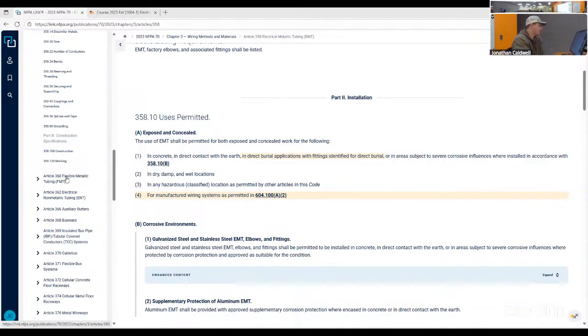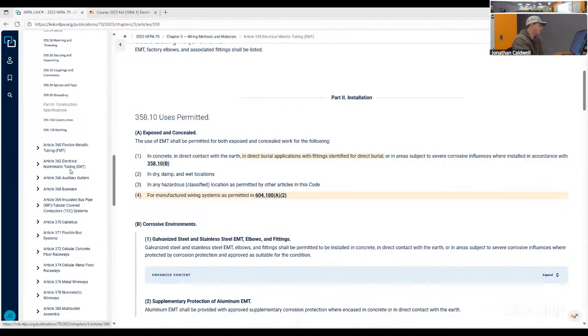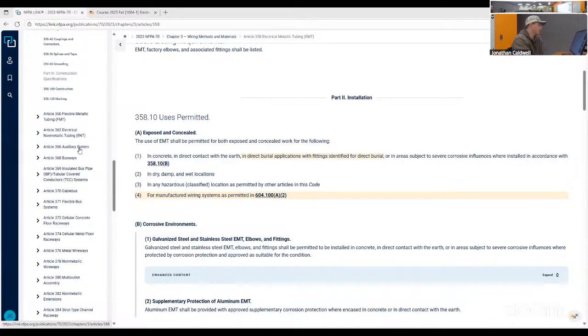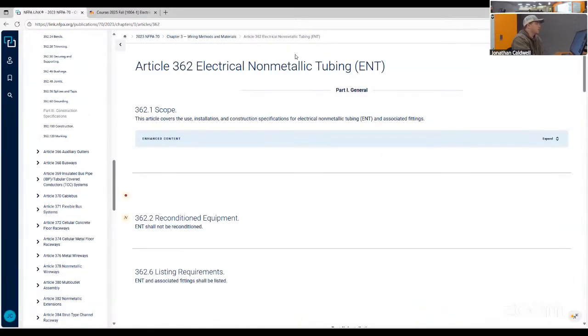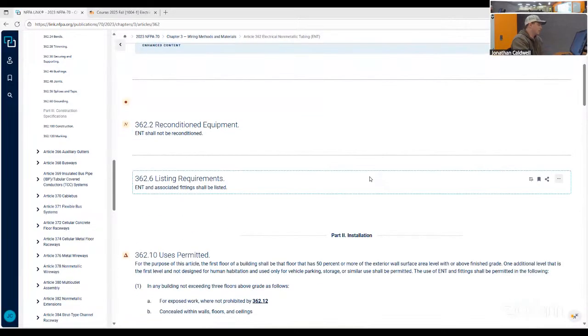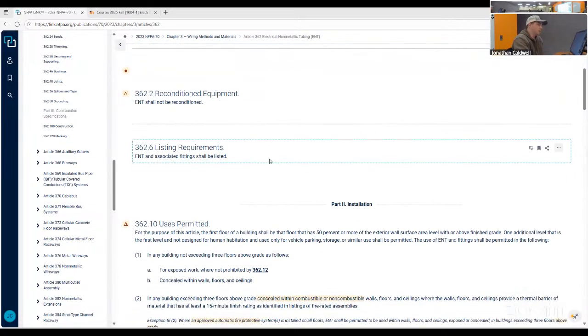Flexible metallic tubing is pretty much the same thing as liquid tight. Same principles apply, same with the grounding part. So I won't cover that. ENT, I'll cover ENT. So ENT, or trade name Smurf tube, that's what a lot of people call it. It shall not be reconditioned, so you can't pull it out of the building and reuse it. ENT and associated fittings shall be listed.